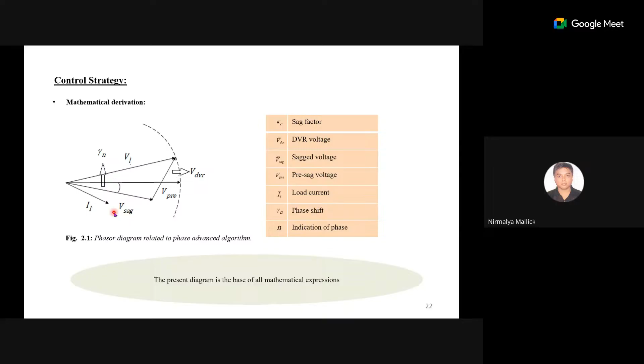Okay, so this is the... let me use my pointer. If there is some voltage sag issue, the VDVR will inject some voltage and rectify the voltage magnitude. But we can see here the VDVR is almost in 90-degree phase with IL, the load current. That means reactive power compensation will happen here, and the real power delivered from the energy storage unit will be minimized or maybe zero.